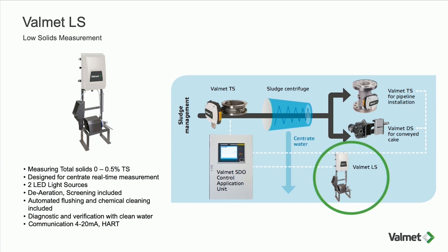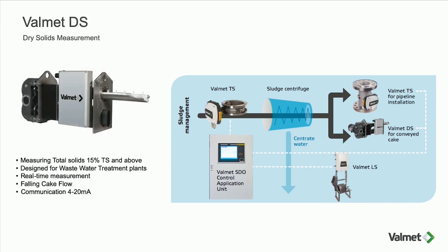The third technology is Valmet DS, designed to measure solids in falling cake flow. It can be installed directly on the outlet of the centrifuge, underneath the centrifuge, or anywhere where there is conveyed sludge falling between conveyors. The sludge falls onto the device, which sits inside the silo, and is taken through and measured using a microwave method. This provides a continuous dry cake measurement on the outlet of the centrifuge.